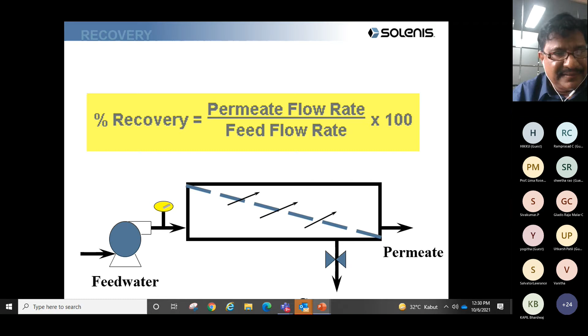The permeate flow divided by feed flow into 100 is 50 divided by 100, which is 50%. So if I had run the RO plant with just the first stage, I would have got 50% recovery. But what I did was take the reject of the RO plant to another RO plant, which is again 25 by 50, which is 50%.